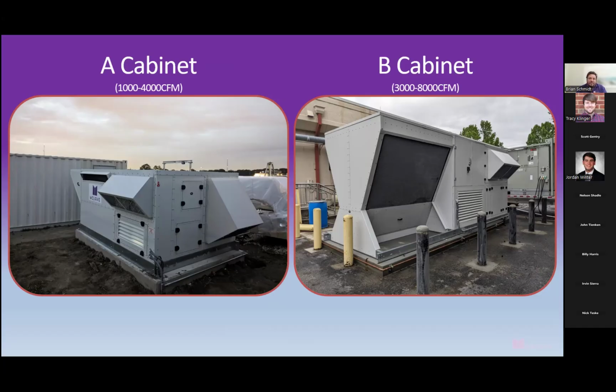In some environments, like the North, you can get 4,000 CFM out of an A cabinet. In environments like the South, where we have a higher humidity concern, you might not be able to get 4,000 CFM out of the A cabinet, so you might have to switch to the B cabinet. So that's why there's that kind of carryover area.